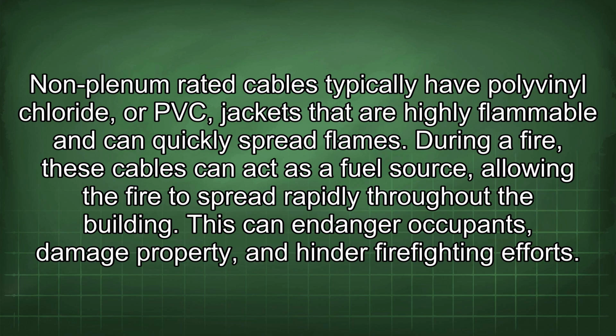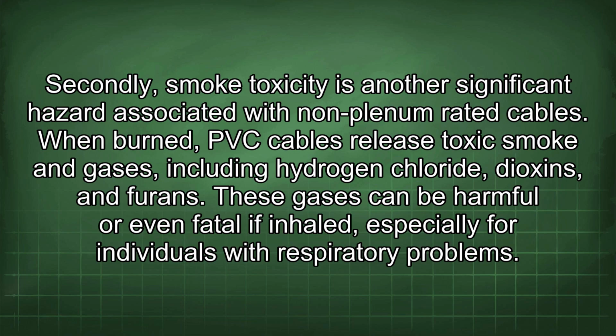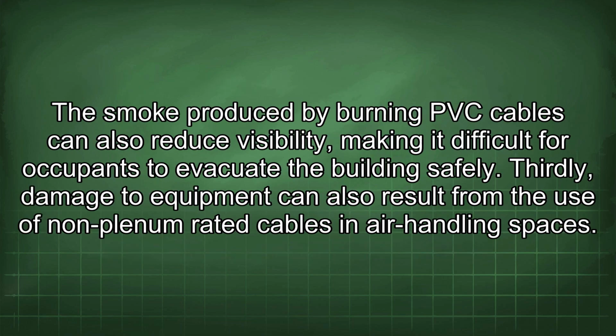During a fire, these cables can act as a fuel source, allowing the fire to spread rapidly throughout the building. This can endanger occupants, damage property, and hinder firefighting efforts. Secondly, smoke toxicity is another significant hazard associated with non-plenum rated cables. When burned, PVC cables release toxic smoke and gases, including hydrogen chloride, dioxins, and furans. These gases can be harmful or even fatal if inhaled, especially for individuals with respiratory problems.